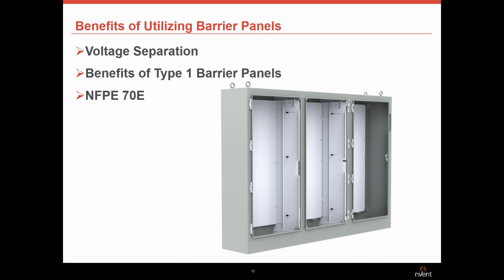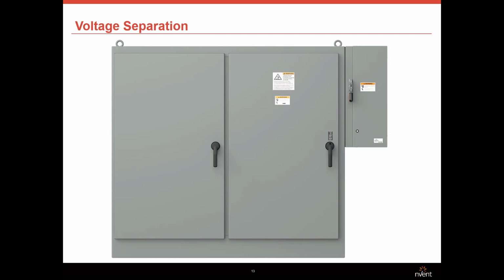The most widely recognized benefit of utilizing barrier panels is going to be creating that Type 1 barrier panel. The creation of a Type 1 internal enclosure helps you with arc flash prevention, and we'll talk about how that complies with NFPA 70E. There is a big push for worker safety because of the OSHA Code 1910 Subpart S. Arc flash safety is a, quote, recognized hazard, unquote, and thus holds severe consequences for employers who have not implemented safety measures.